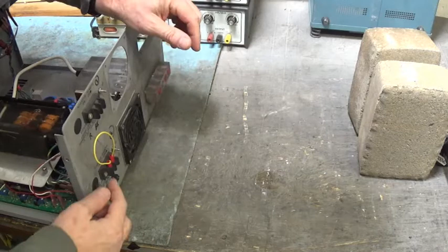Here we're at the back side of the charge master. There's an enable input right here that you have to jump out. I jump it out with this wire right here. You have to jump this out, otherwise the charge master will not provide the high voltage output.